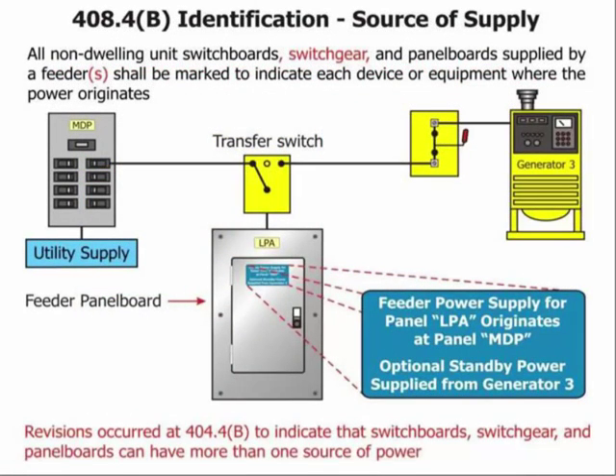Still in Chapter 4, for non-dwelling units: if a panel has more than one source of electrical supply—for instance, tied to both the utility and a generator via a transfer switch—a label must now be placed on the panel indicating that optional standby power is supplied from a specific generator. During normal operation the utility provides power, but if the utility fails and the generator kicks in, this label is especially important for troubleshooting or maintenance during a transfer.